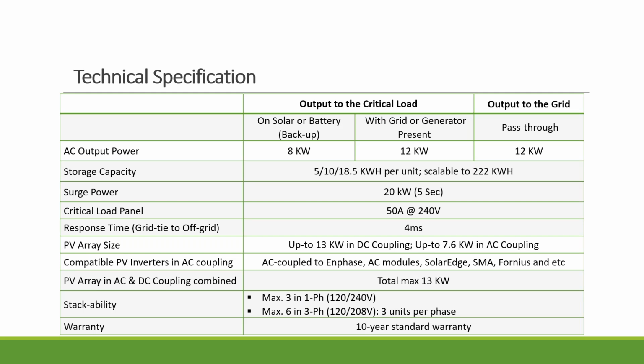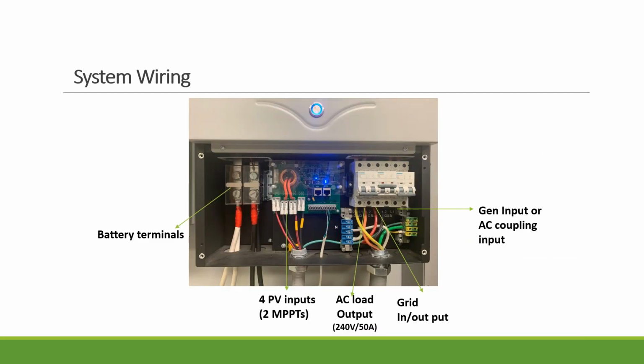How the inverter works is, you have an on-off. So when you put on solar, it's an 8K continuous draw from the battery and solar. And if it's connected to the grid, then you can push 12 kW to the backup load panel. So you will choose a 50 amps critical load panel. It has built-in auto transfer, so all the power electronics are in one unit. You can do AC/DC or even combine them together.